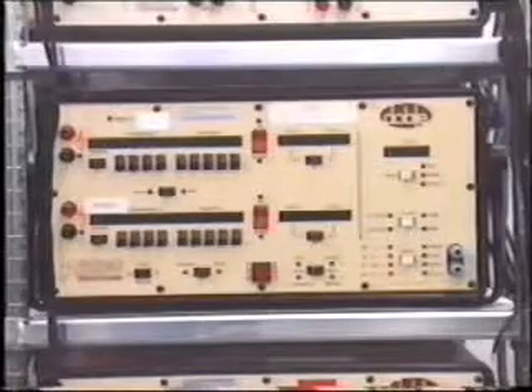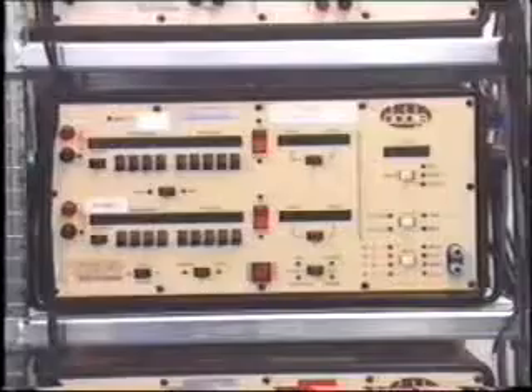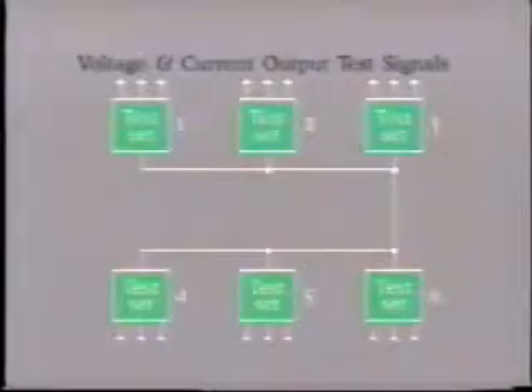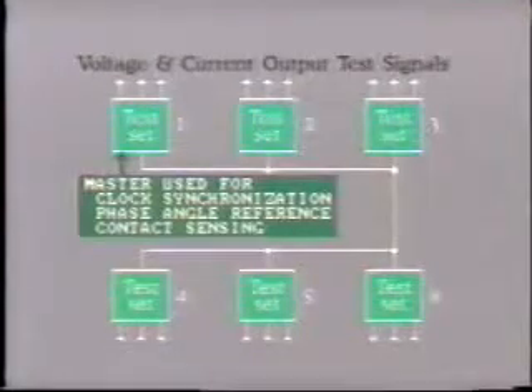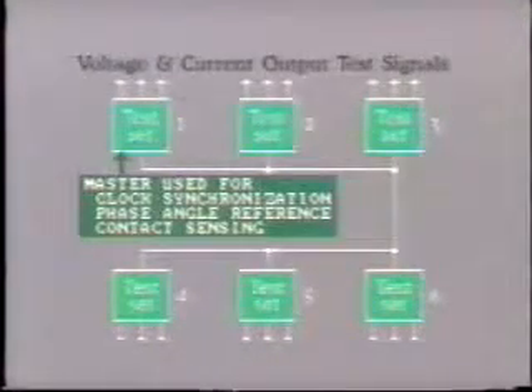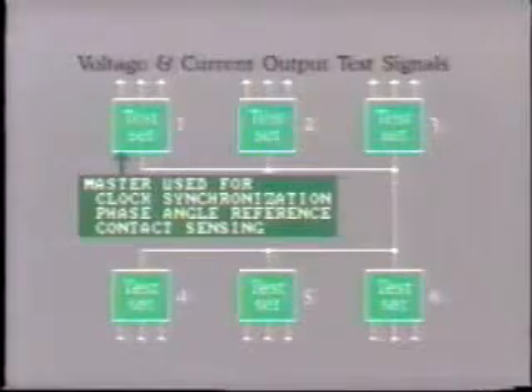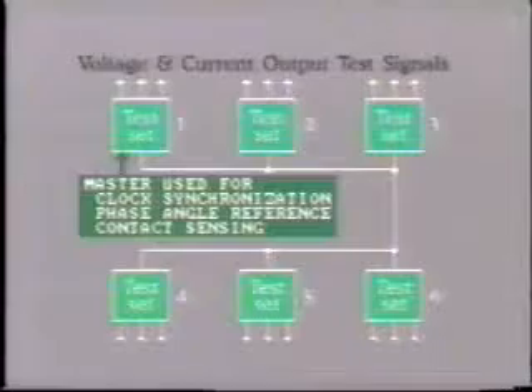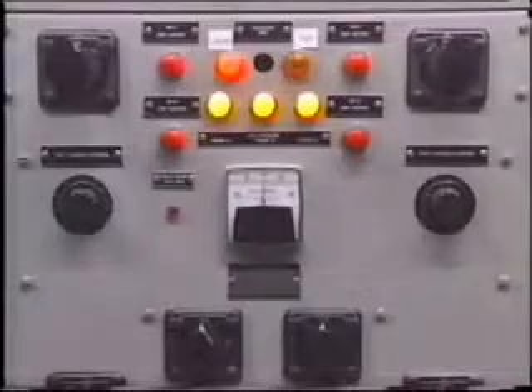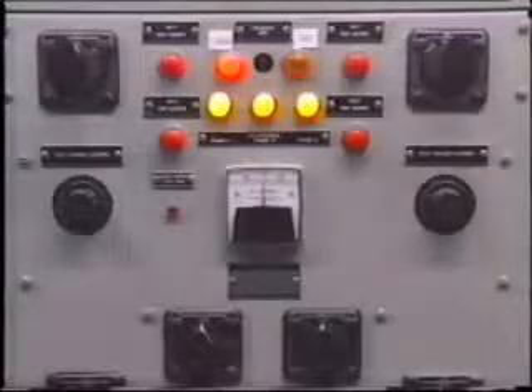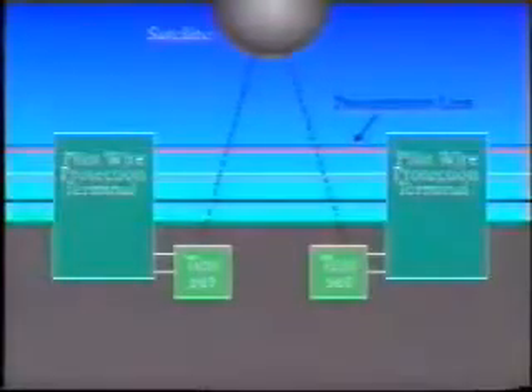What can these units do that previous test sets cannot? Well, quite a bit, actually. Up to 6 units can be connected together, with one unit acting as the master for clock synchronization, phase angle reference, and contact sensing. 6 voltages and 6 currents can be turned on simultaneously. Back-to-back line pilot protection terminals can be tested for any type of fault. They can also be satellite synchronized for end-to-end line protection testing via computer.